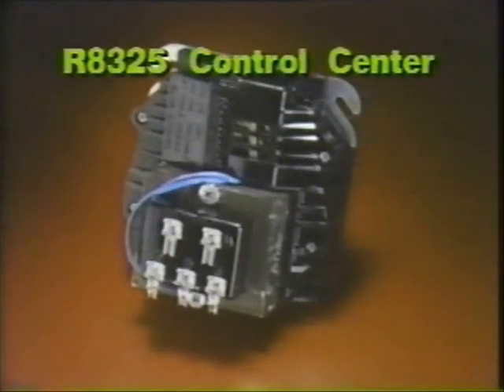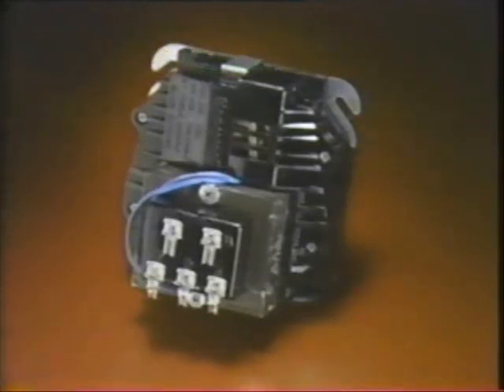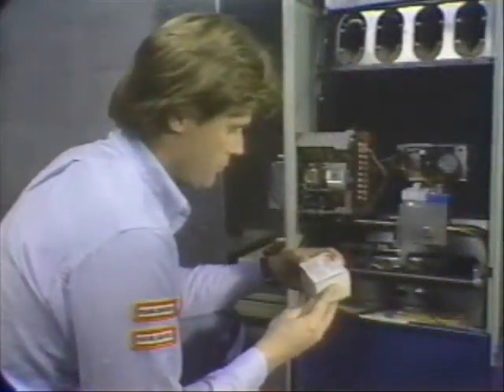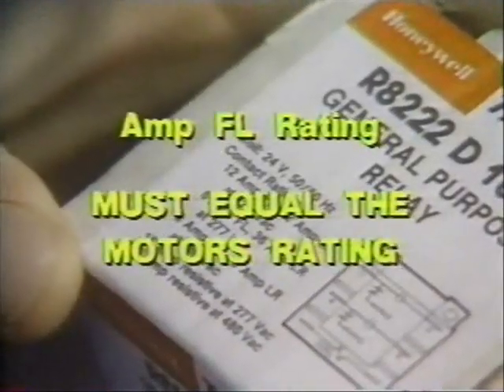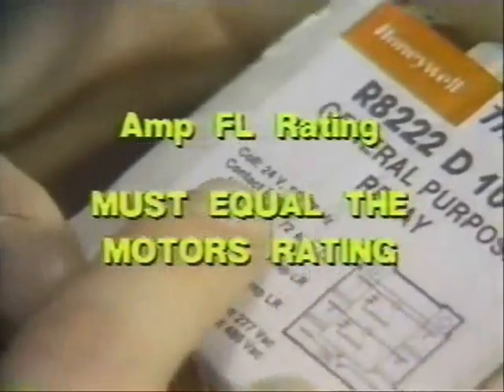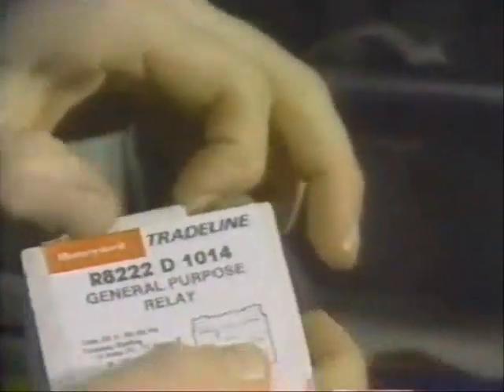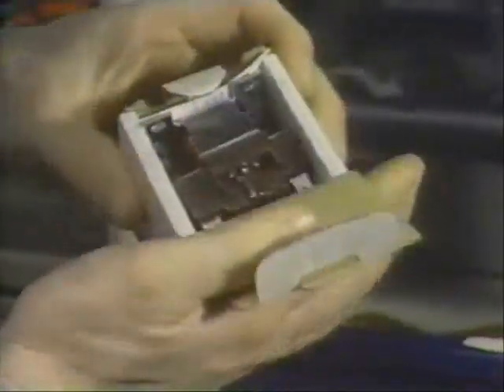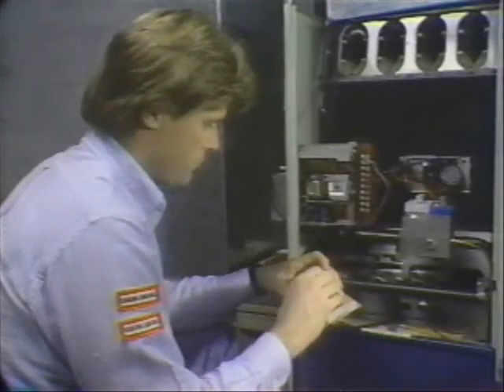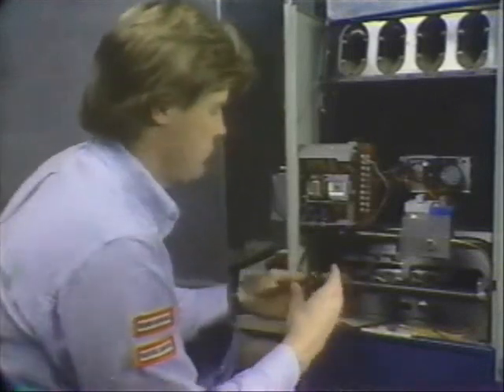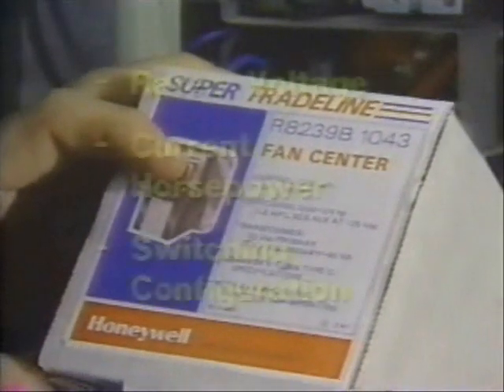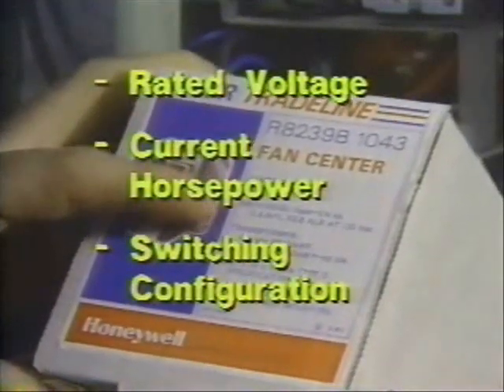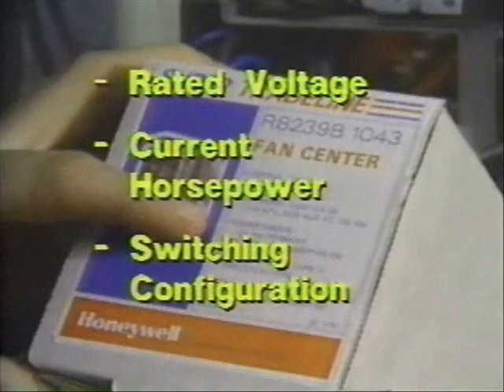The R8325 control center is basically the same as the 8239, but with a higher rated transformer and a lower current relay, it has more usable VA. When selecting a replacement relay for controlling a motor, the contact rating, amperage full load, must equal or exceed the motor's rating. Otherwise, the contacts will burn out very quickly and possibly cause serious damage to the motor. When matching a fan relay or center to a fan system, you should know the rated voltage, the current or horsepower rating of the contacts, and the switching configuration.